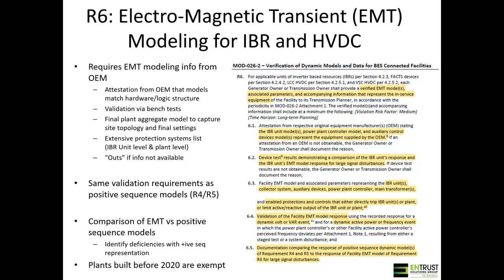A lot of times, frequency response is kind of termed, especially from the plant controller, as not a subject of interest to EMT modeling, just because it happens over spans of like 10 plus seconds usually, or it might be shorter than that. But things like fast frequency response, synchronous machine emulation type behavior, is something that could be captured and would be relevant to capture.